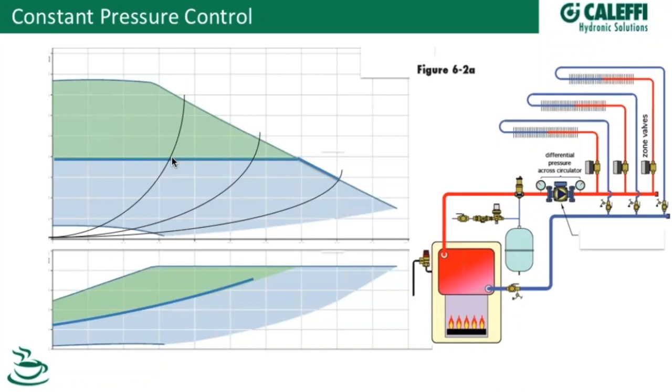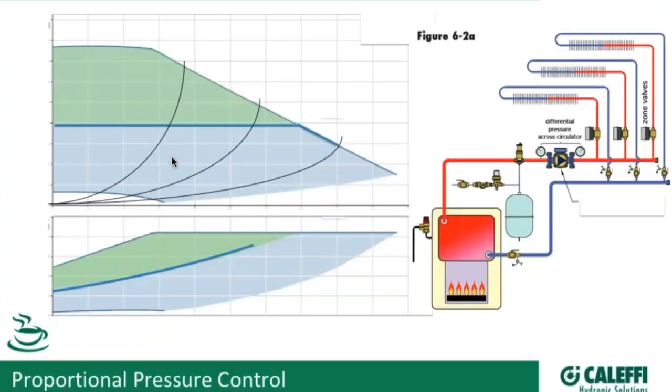Constant pressure differential is a good mode. With three zone valves open, the pump runs to its max curve at 100% speed, intersecting the system curve. When a second valve closes, the pump exceeds the set point for constant differential, which tells it to slow down until it intersects the next system curve. The same occurs when another valve closes — the pump recognizes the pressure increase and slows down to maintain the set point. A lot of manufacturers have moved to other control modes in efforts both to get more efficient and to have a smoother operating system without creating additional pressure that isn't needed.